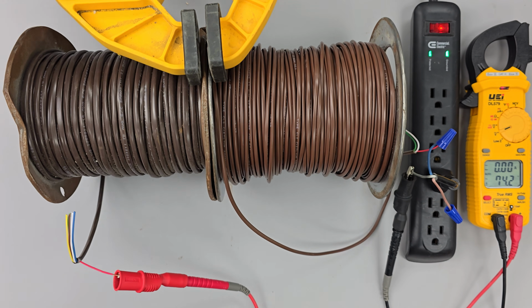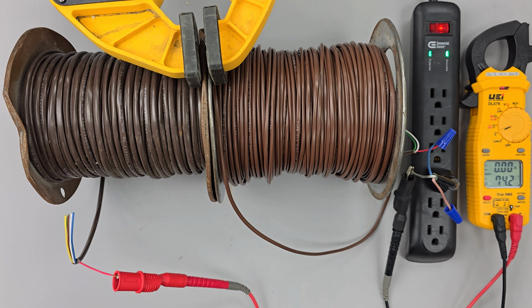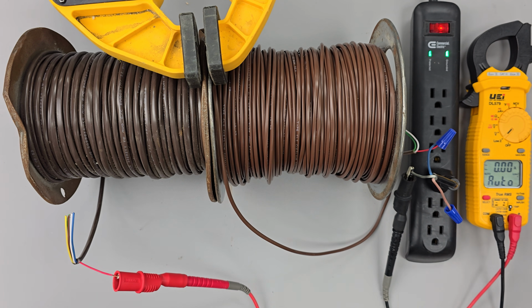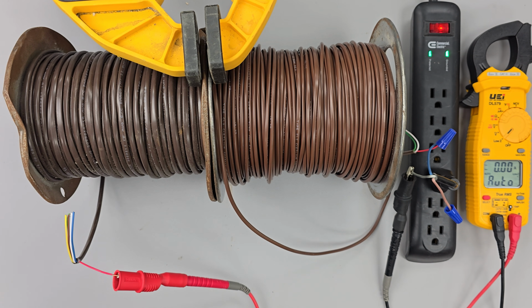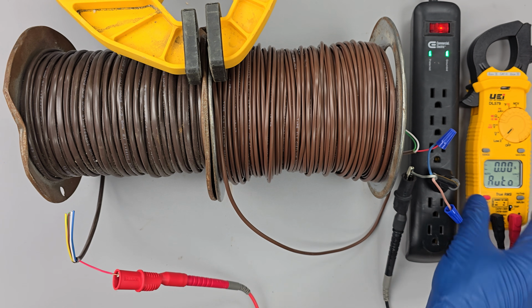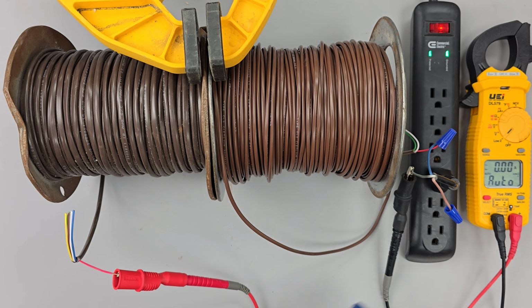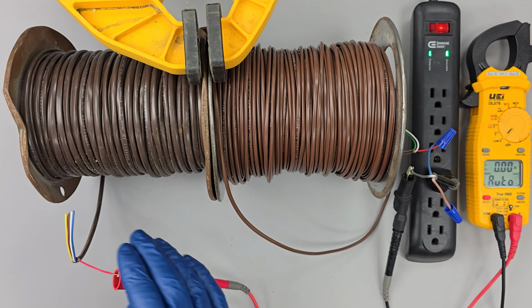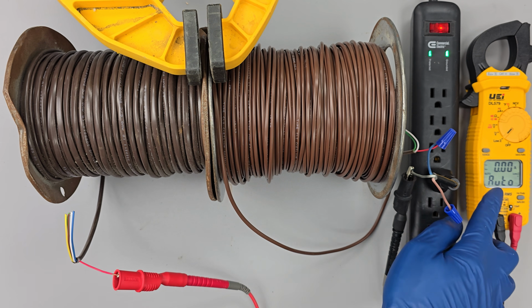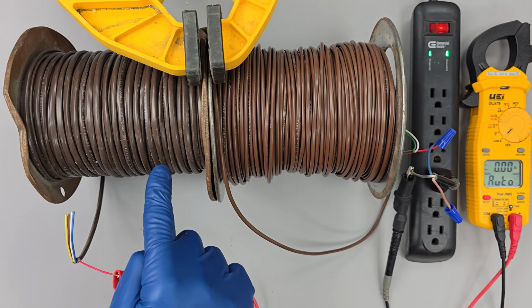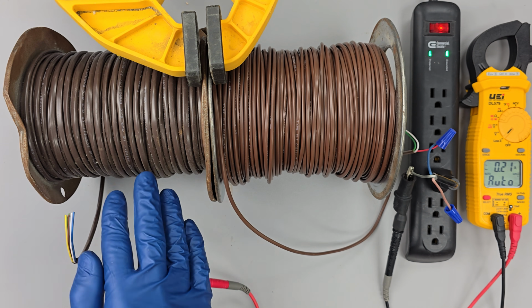And I want to show you that even if we go down to the low Z function, we're then not going to have any voltage, even though we have this metal crimped together. So that's how the low Z function works. It cancels out that very, very small amount of electrical power that's present so that your reading is true, because that 70 volts does not have enough power to support a load.